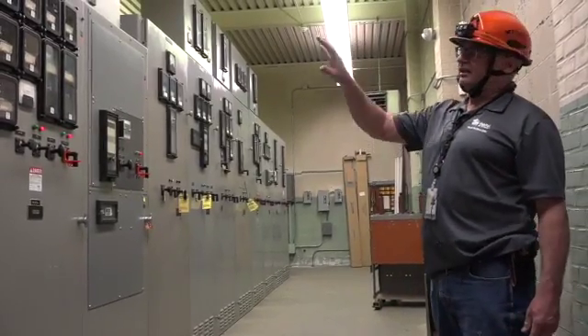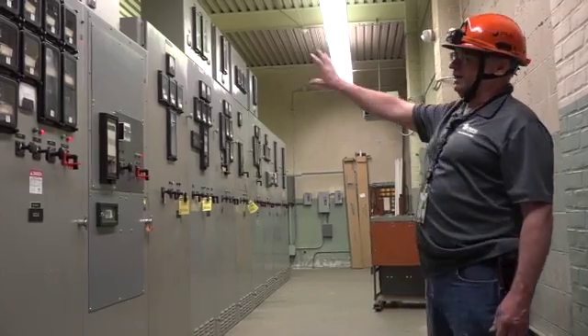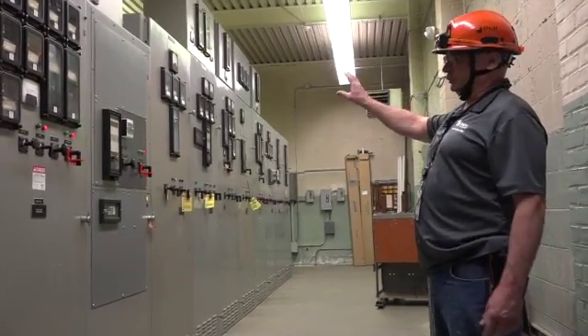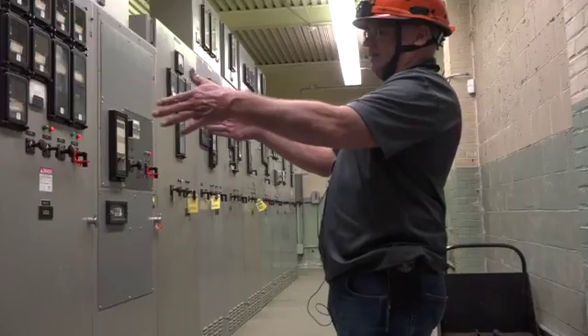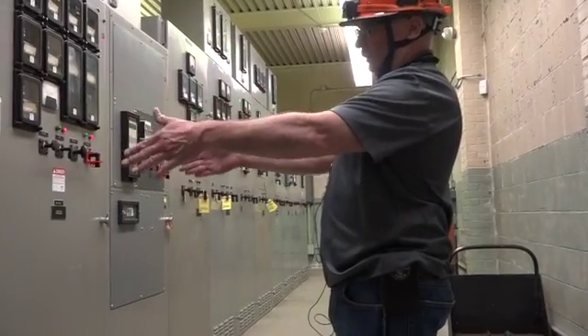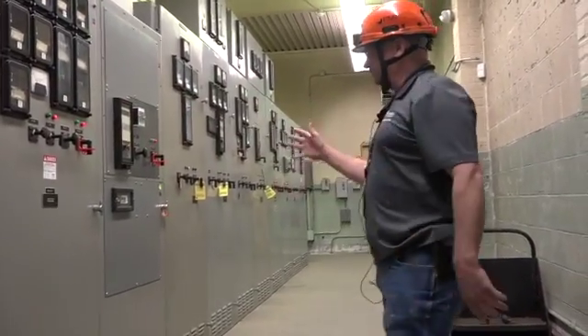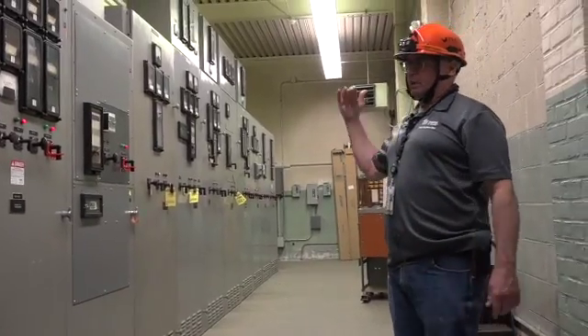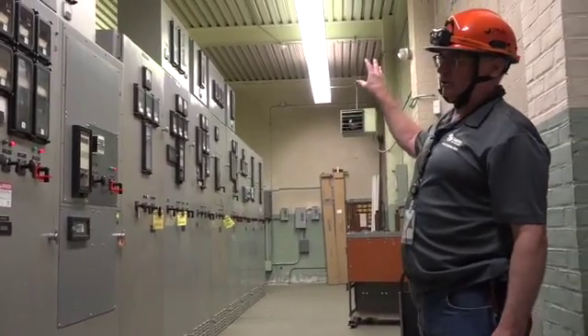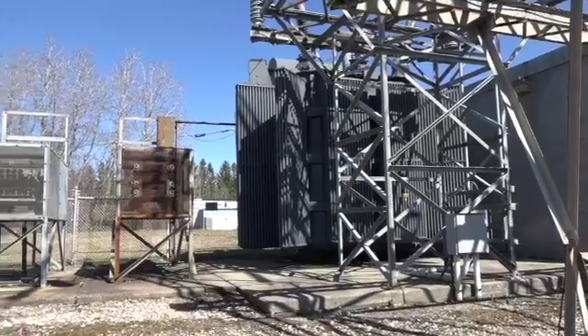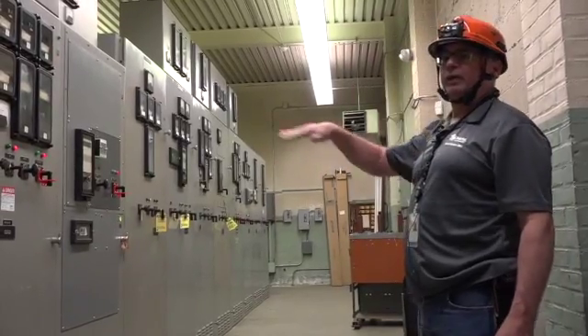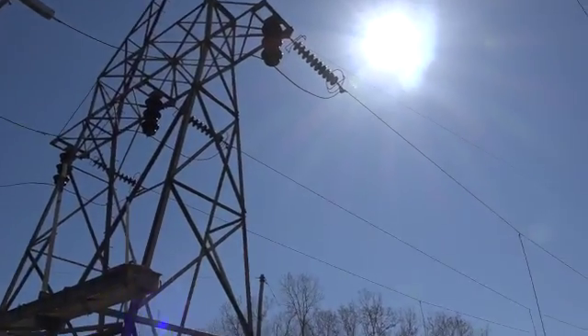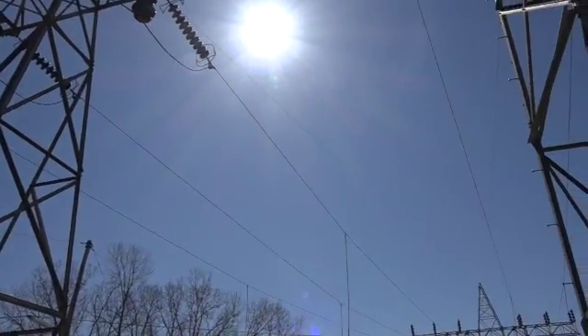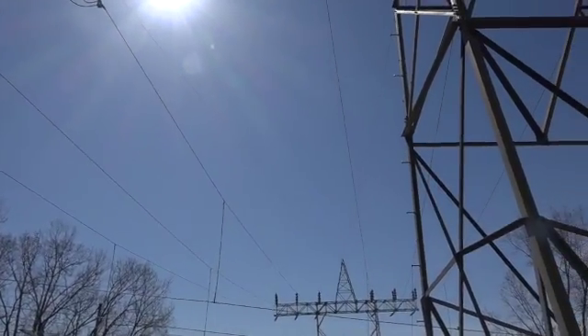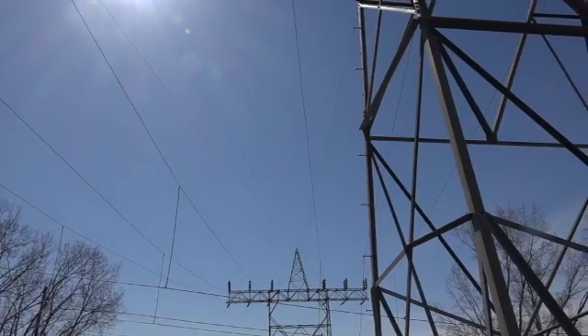There's 13,800 volts inside of this metal clad gear that's feeding circuit breakers. Each one of these doors, there's a circuit breaker inside that receives power from the main transformers and then goes through the circuit breaker and then goes underground going out. If it was a utility, it would be going out and feeding all the streets out in your community, power going up on the telephone pole.